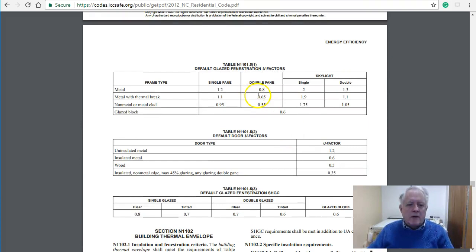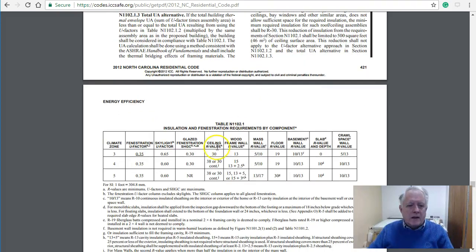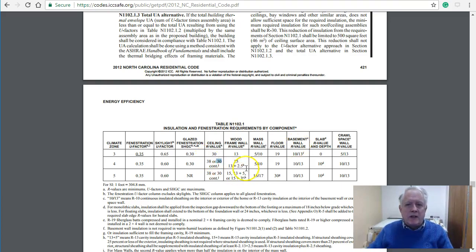We're in Climate Zone 4A. The requirements you'll need to copy from this chapter into E1 are listed here. For example, you'd copy these values — don't copy both rows. Your ceiling would be R-38 between joists or R-30 continuous. R-30 continuous means it would be on top of the roof deck or between the joists and ceiling finish — not interrupted by the joists. This other value is between the joists, or between the joists plus continuous.